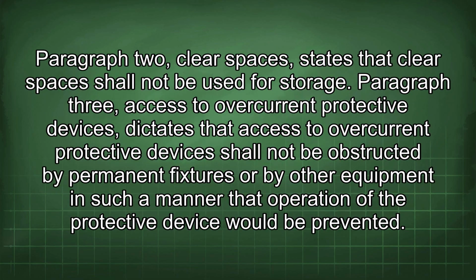Paragraph 2, Clear Spaces, states that clear spaces shall not be used for storage. Paragraph 3, Access to overcurrent protective devices, dictates that access to overcurrent protective devices shall not be obstructed by permanent fixtures or by other equipment in such a manner that operation of the protective device would be prevented.